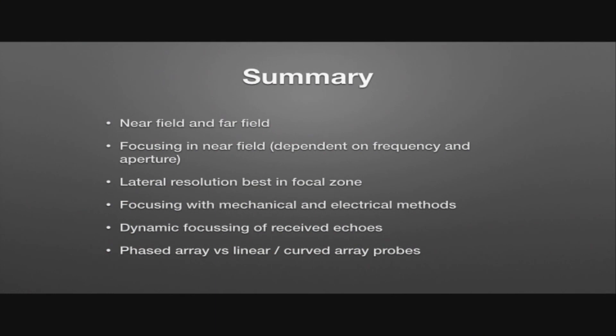So in summary, the ultrasound beam is going to have a near field and a far field. Focusing can only happen in the near field and that is dependent on frequency and aperture. In the focal zone, this is where the resolution and the intensity is going to be the best. Lateral resolution is best in the focal zone, as is axial resolution. Axial resolution is normally better than lateral resolution. Further focusing can occur with mechanical means, so that's using a curved probe or a lens, or with electrical means, where we get delays in different portions or different elements which can be stimulated at different times to other elements.